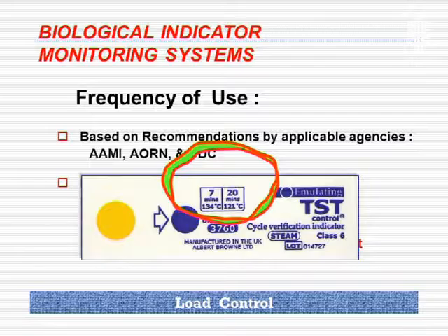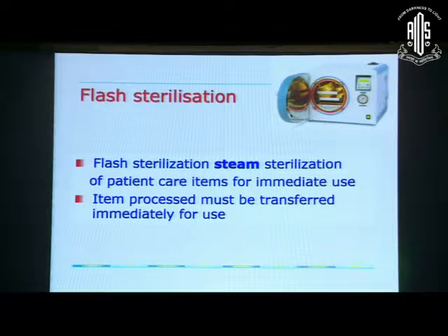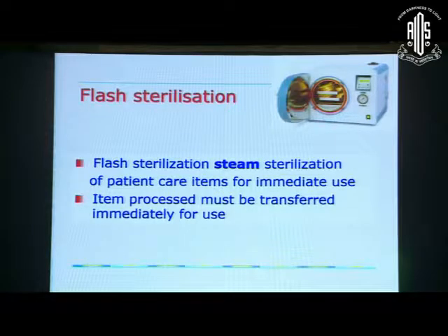The TST — the Class 6 chemical indicator — is practically as good as the biological indicator. Please start using this. Flash sterilization is meant for instantaneous use only. It cannot be stored because there is no drying cycle; the instruments come out wet. Use flash sterilization only for emergencies.